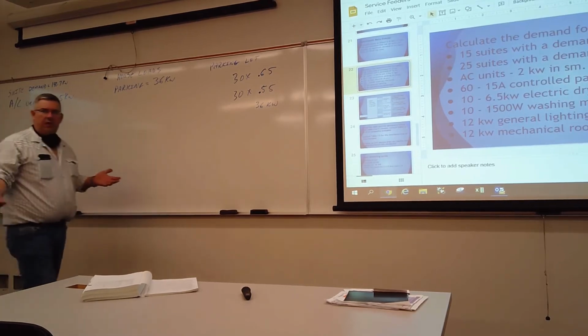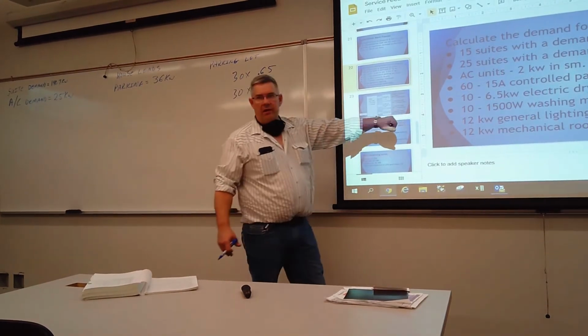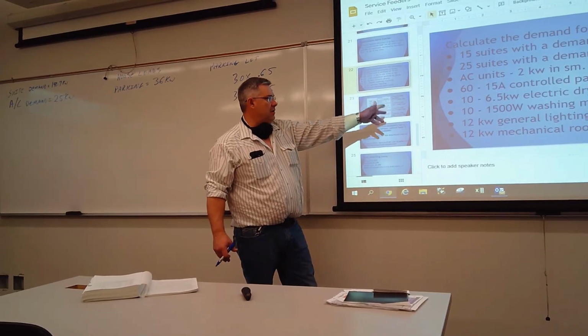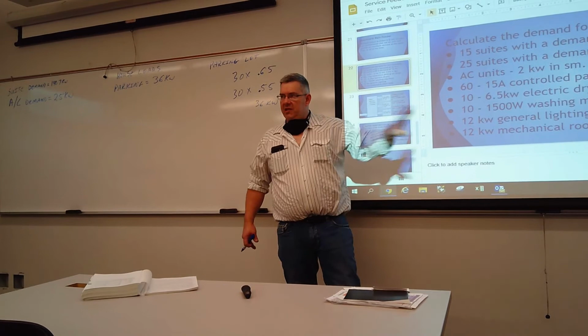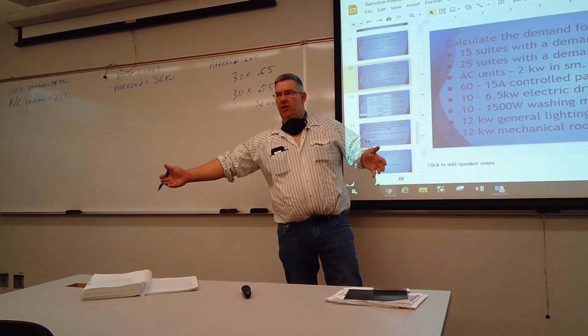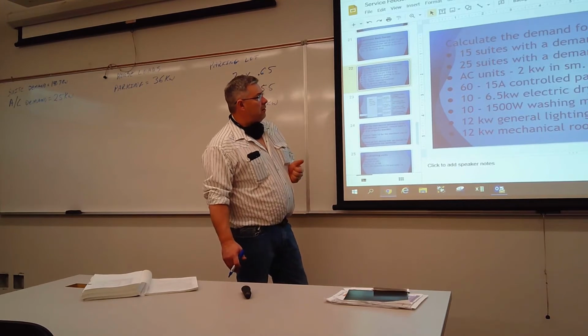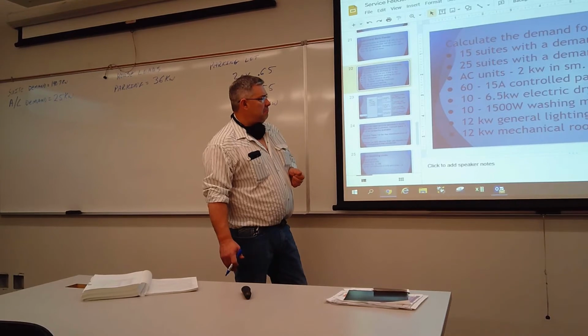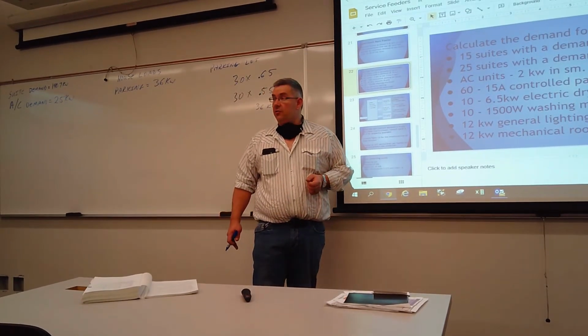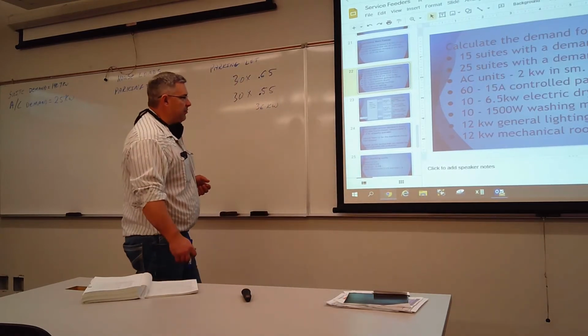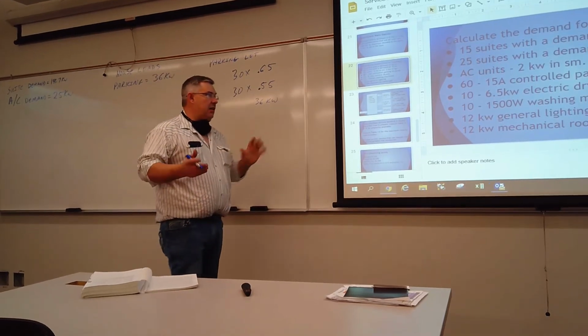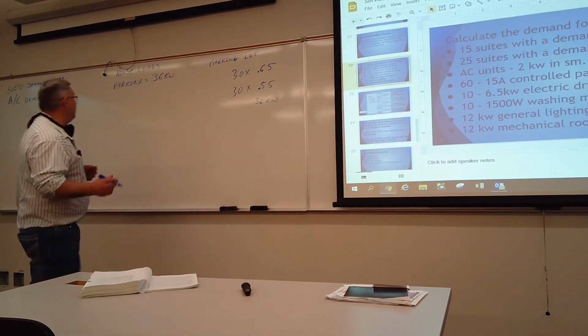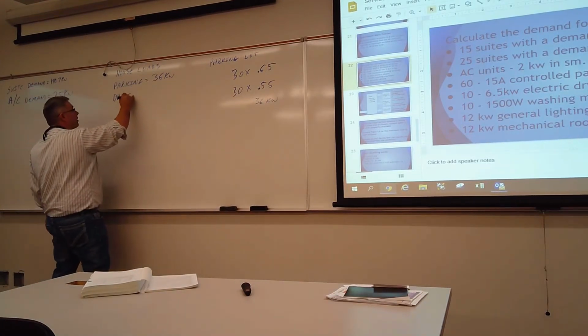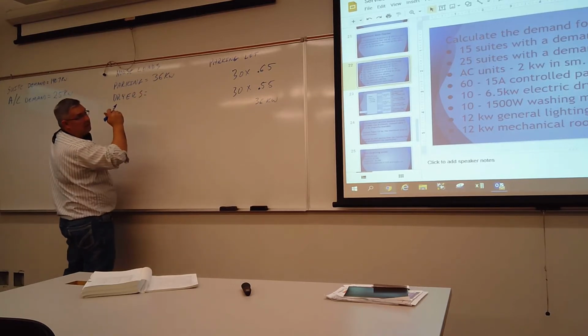Okay, 6.5 kilowatt electric dryers. If they were in the dwelling unit, we'd have added them in at 6,000 watts for the first 6 kilowatts, and then 25% for that 0.5. But these are not in the dwelling units. These are just in a community laundry facility. With 40 suites in an apartment building and 10 dryers and 10 washing machines, they're probably going to get used fairly regularly, right? That's a lot of people doing laundry in 10 machines. So because of that, we just add them up at face value. It's simple enough. Dryers is going to be 65 kilowatts.